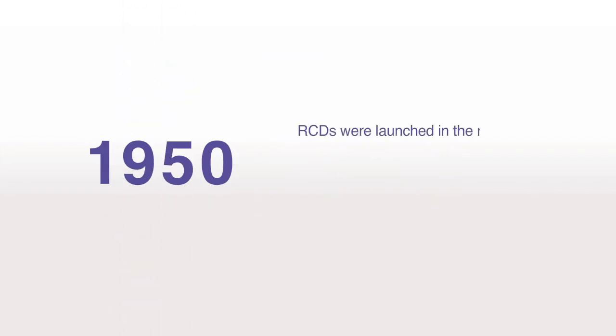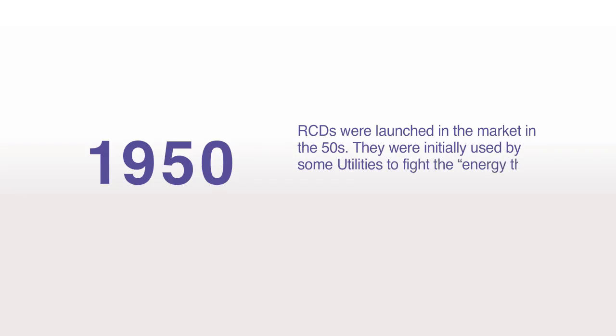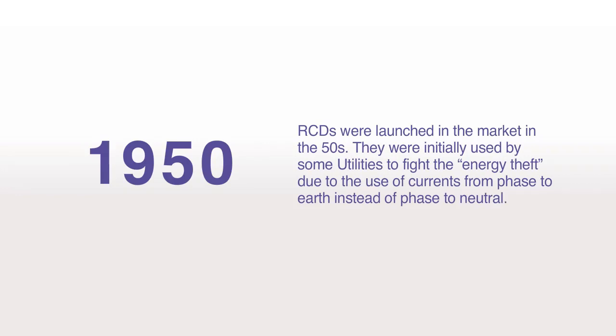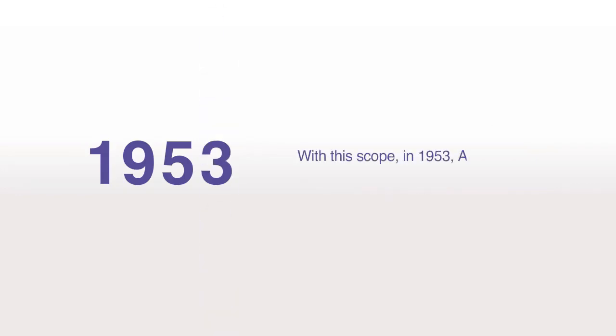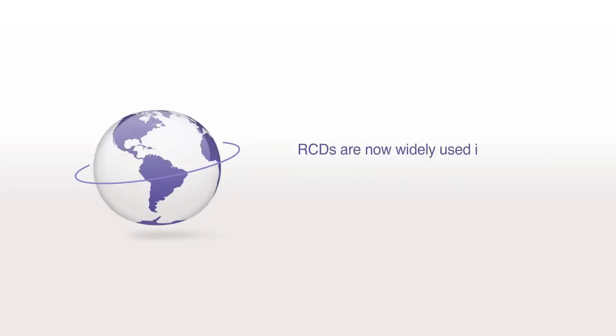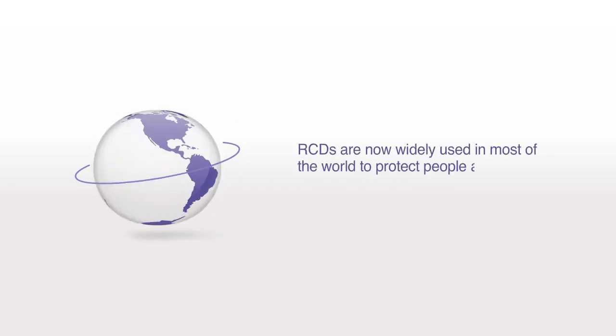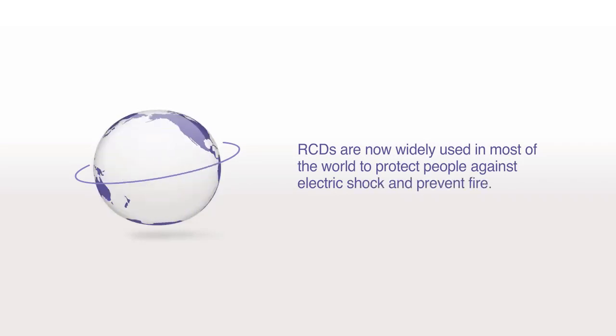RCDs were launched in the market in the 50s. They were initially used by some utilities to fight the energy theft due to the use of currents from phase to earth instead of phase to neutral. With this scope, in 1953, ABB built the first low-sensitivity RCD. And in 1956, a device with high sensitivity. RCDs are now widely used in most of the world to protect people against electric shock and prevent fire.